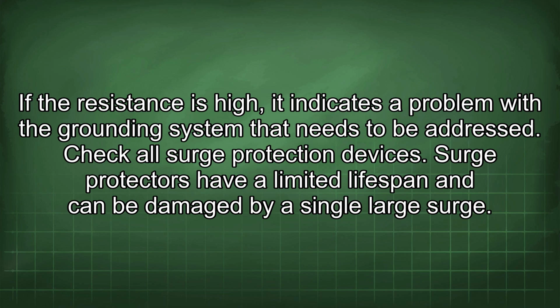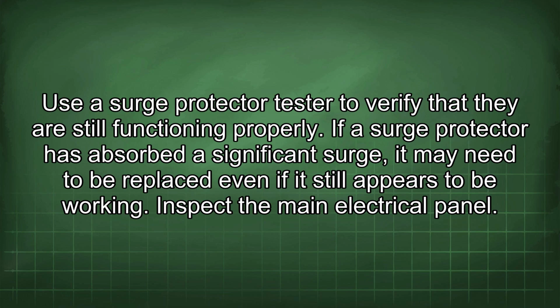Check all surge protection devices. Surge protectors have a limited lifespan and can be damaged by a single large surge. Use a surge protector tester to verify that they are still functioning properly. If a surge protector has absorbed a significant surge, it may need to be replaced even if it still appears to be working.